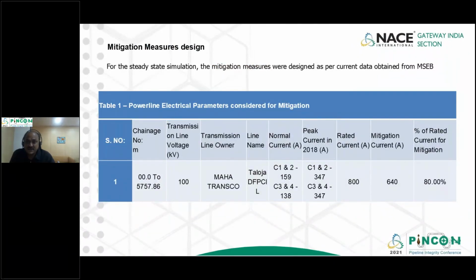So for a steady state simulation, the mitigation measures were designed as per the current data obtained from MSEB. Between chainage 0 to 5757, the transmission line voltage was 100 kV, and this is Maharashtra Transco, whatever you call Maharashtra MSEDCL, at Taloja. The peak current we found in 2018, the rated current, the mitigation current, and the percentage of rated current for mitigation was 80%.